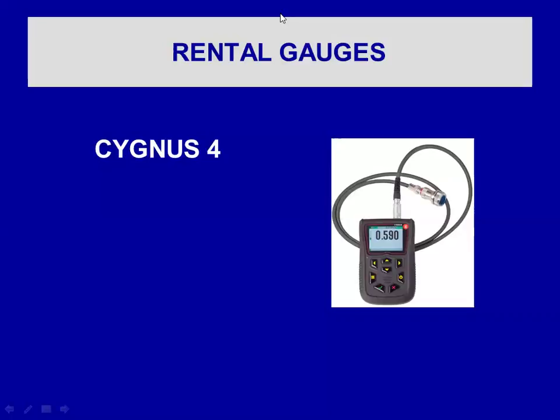If it's not enough information, put the thickness gauge away. For pipelines, if this isn't enough, mark the pipe and go get a flaw detector, get a radiographer, get somebody to take a picture of it. Do something else. Thickness gauges are only thickness gauges, they're not designed to look at discontinuities, cracks, and that sort of stuff. They give you an indication.